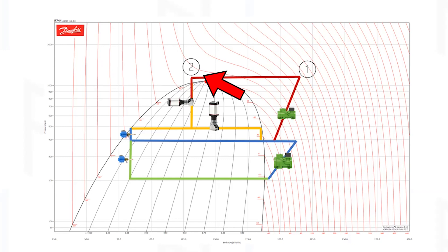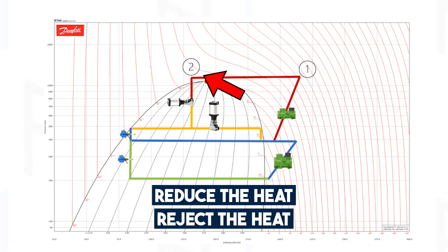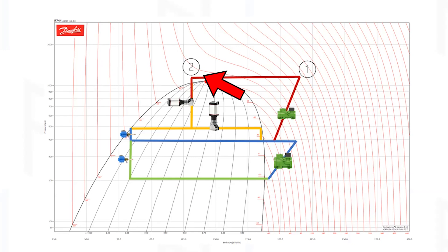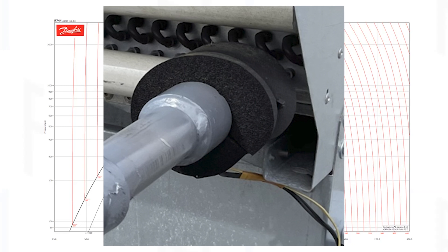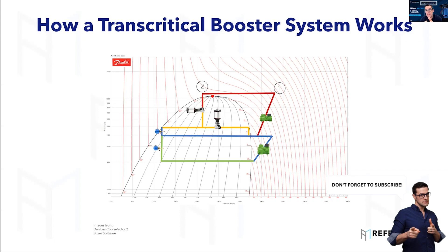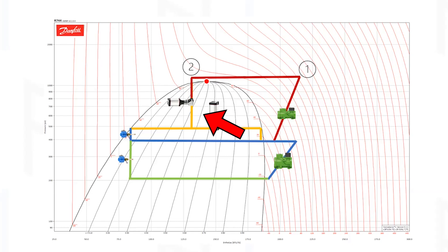And then as it goes through the gas cooler, it's cooled down. So from one to two, as you see on these points here, when we go from one to two, this is actually where the gas cooler condenser is, and 2 is at the outlet. So this is actually the heat that has been removed from the refrigerant in that gas cooler. And in transcritical mode, all you can do is reduce the heat, reject the heat as much as possible, because you're not going to turn that into a liquid or a gas. That really only happens if it's a condenser, if you're in that subcritical zone or mode, you're below that critical point.